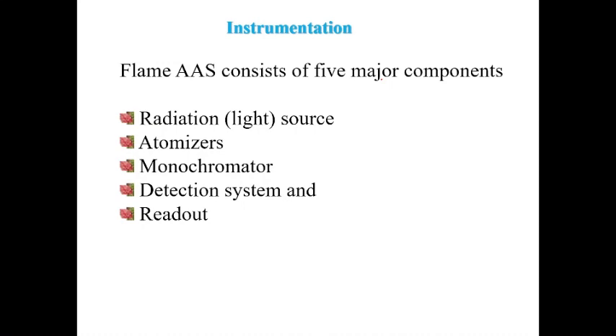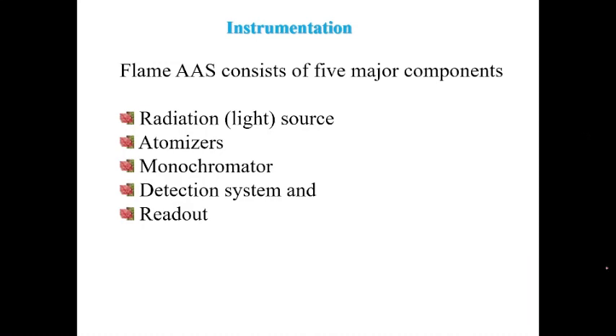The major components of flame AAS are: first, the radiation source — mostly the hollow cathode lamp; second, the atomizer — to convert sample particles into atoms; third, the monochromator — to select the unique spectral line of interest and filter out other wavelengths; fourth, the detection system — mainly the photomultiplier tube; and fifth, the readout device.